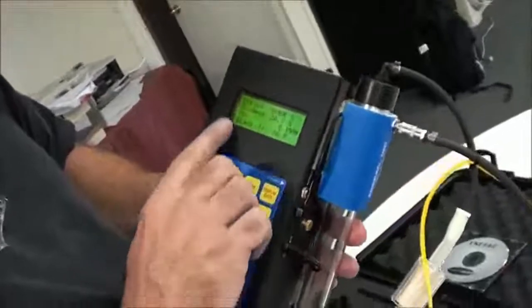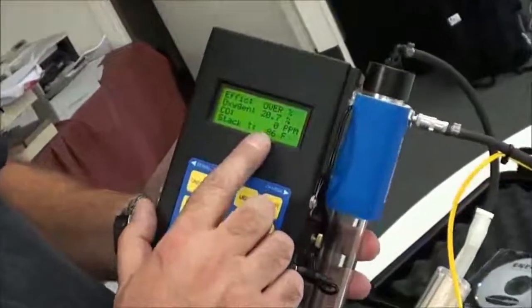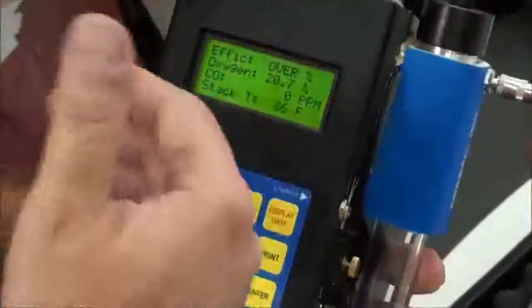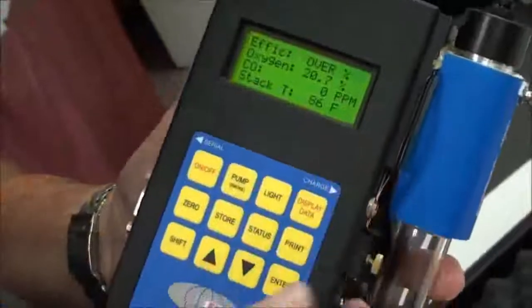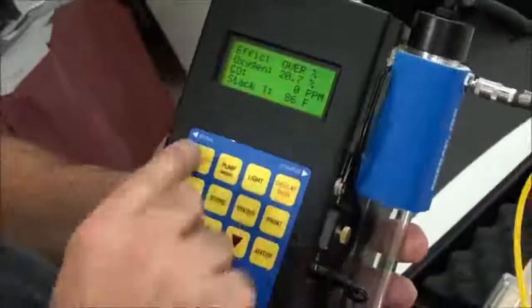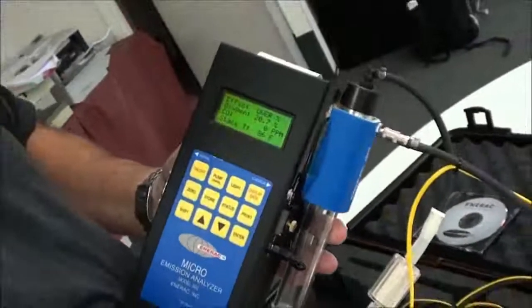Keep in mind that the tip of that probe is going to be very hot, so don't put it on anything that you don't want to damage. Keep it away from plastic, keep it away from your skin, your clothes, until it cools down. Let the unit run, let it purge. You can put it back on oxygen, the CO, or any of the readings, and just watch it and wait for it to come back close to ambient again. At that point, you're done. You can turn the unit off, disconnect your hoses, and put everything away. And that's it. It's that simple.